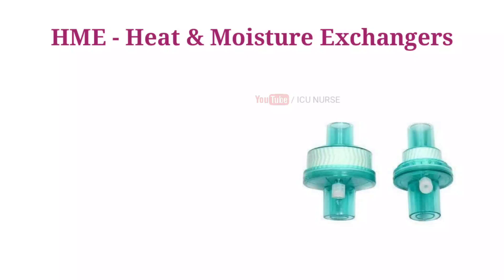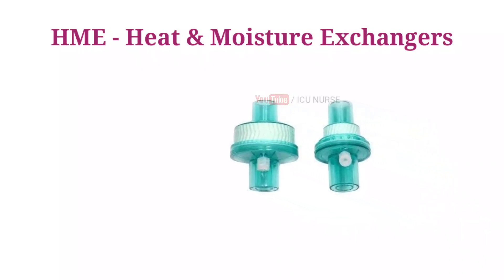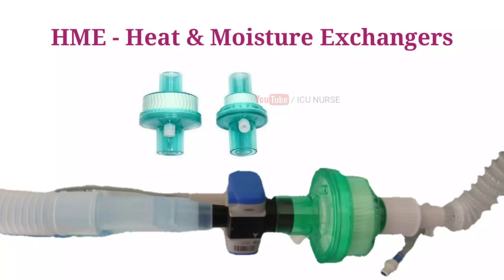HME stands for Heat and Moisture Exchangers. HME filters are devices used in mechanically ventilated patients, intended to help prevent complications due to drying of the respiratory mucosa, such as mucus plugging and endotracheal tube occlusion. HME filters are passive humidification systems that retain heat and moisture from the patient's exhaled gas, providing effective protection against bacteria, viruses, and moisture droplets, helping protect the patient, equipment, and breathing circuit from contamination.